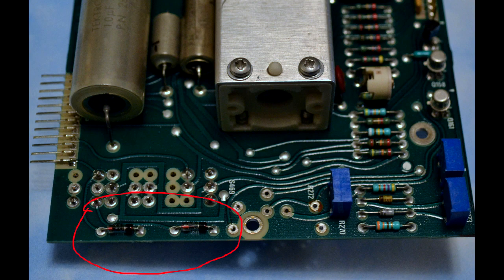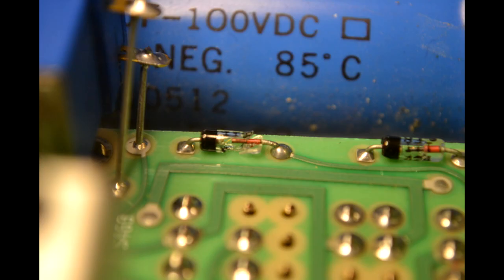CR374 was open, it was cracked as can be seen here. Stress from the lead forming during assembly probably disposed it to crack when the instrument was subject to shock.